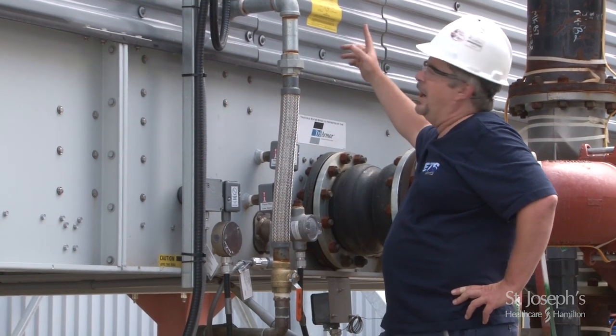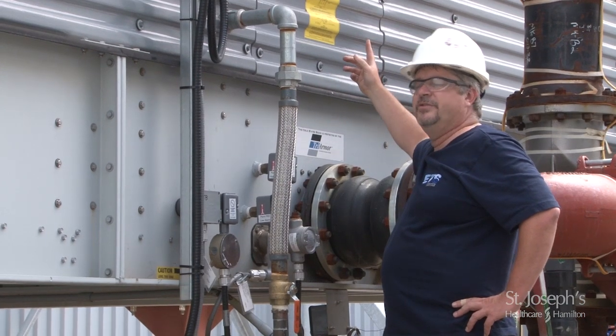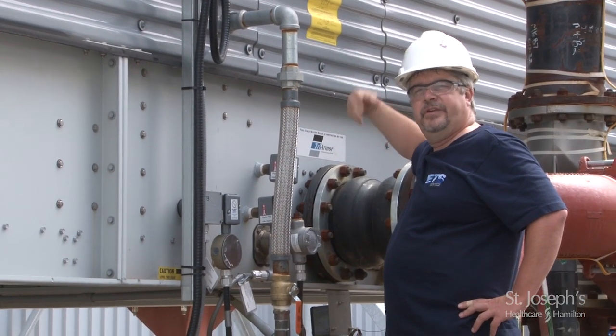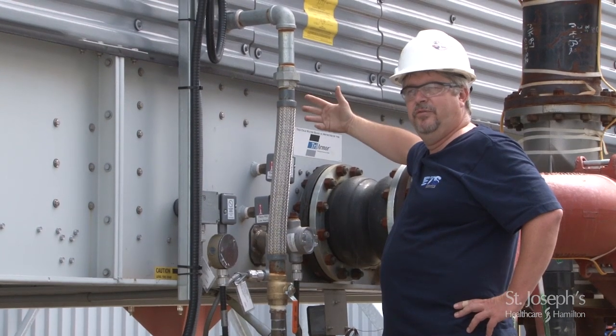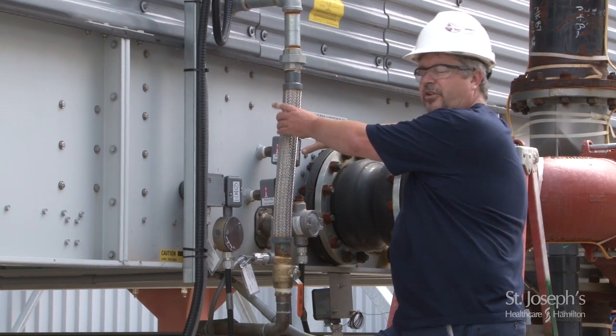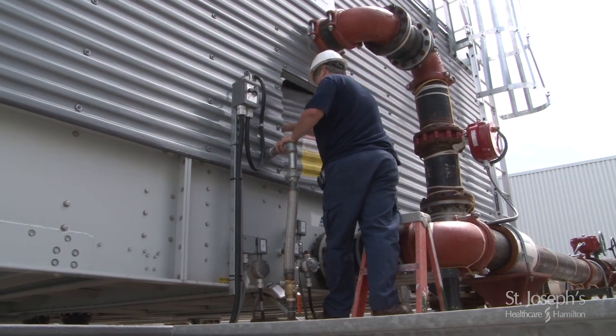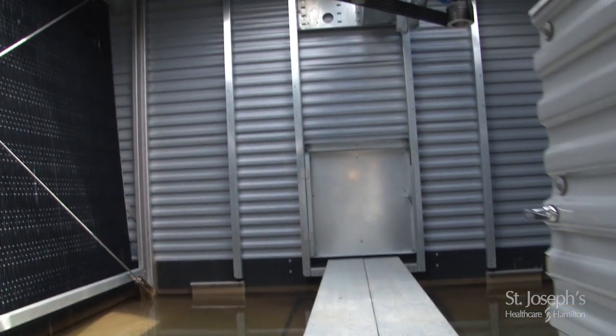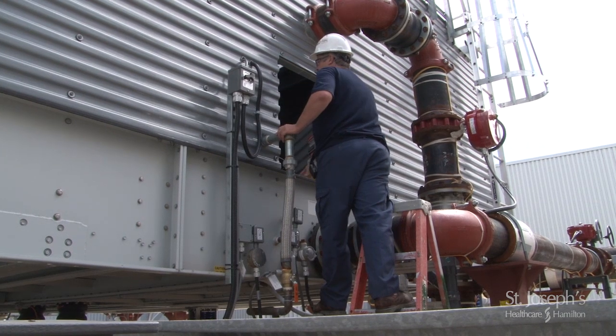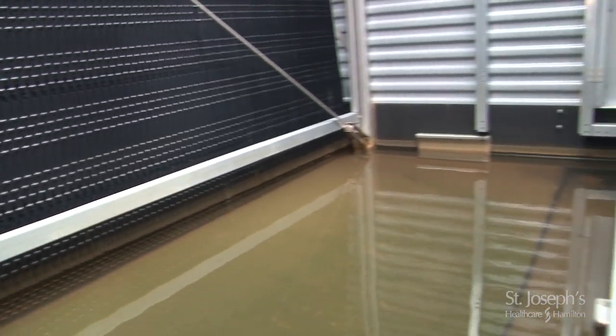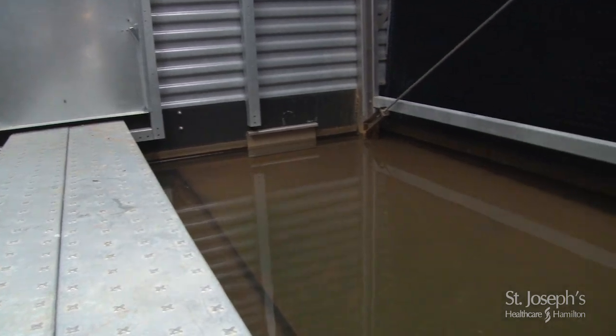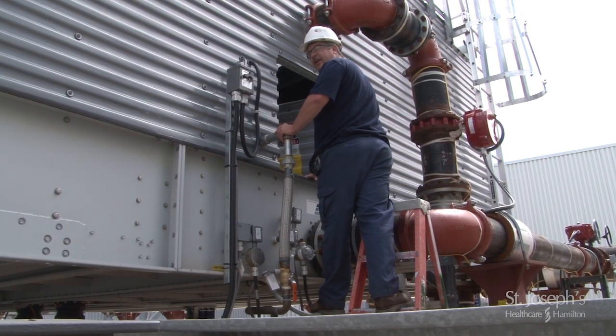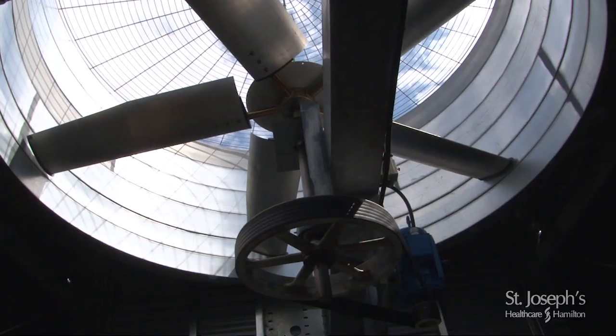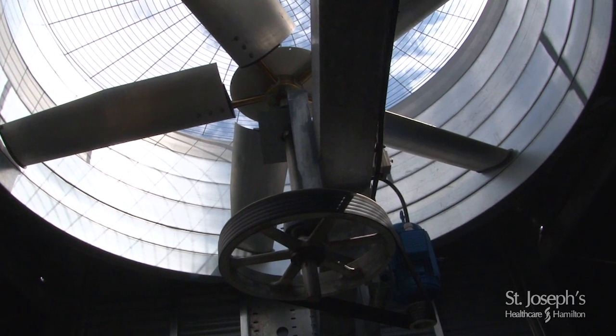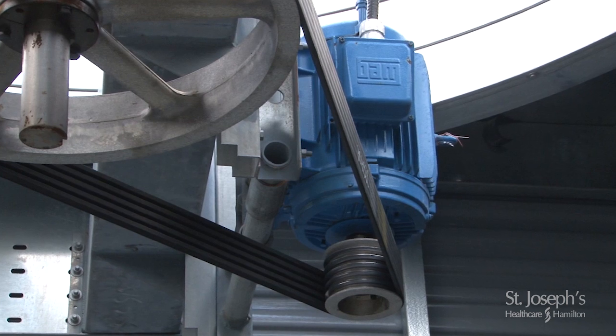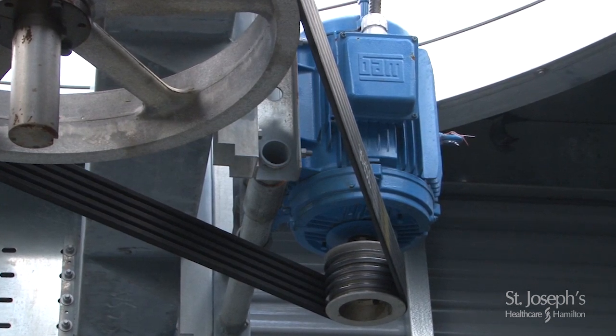The next thing I would like to do is open up the access door and have a look inside at some of the things we would be looking for when we're looking at these cooling towers as far as maintenance is concerned. Once you open the access door to the cooling tower, the very first thing you'll notice is that there's a service platform inside, which allows you to get inside and do work internally within the cooling tower. What we're looking at here right now is the motor and pulley assembly along with the belt that drives the fan in the cooling tower.